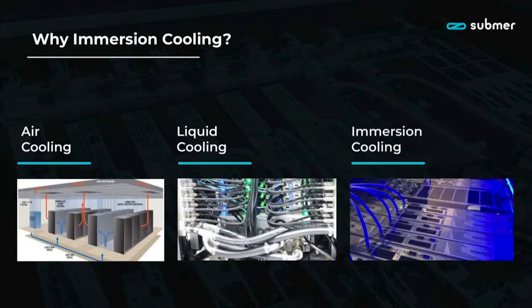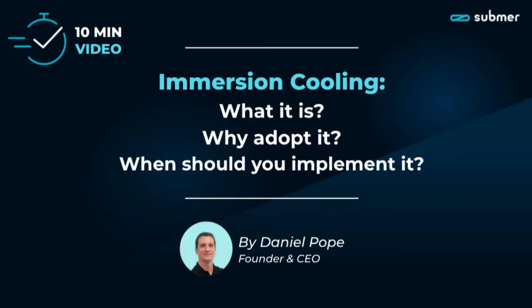Immersion cooling, which is the space where Submer operates in, is a bit of a different approach. We completely submerge the IT equipment into a dielectric fluid that we've developed. That liquid changes the medium around the servers, captures the heat, and transports it in a very efficient way. It protects the IT hardware, and overall it allows us to slash the energy costs and increase the density. It also brings some other side benefits: if I deploy immersion systems in the edge, I have this protective barrier around the hardware, which is very beneficial in harsh environments.